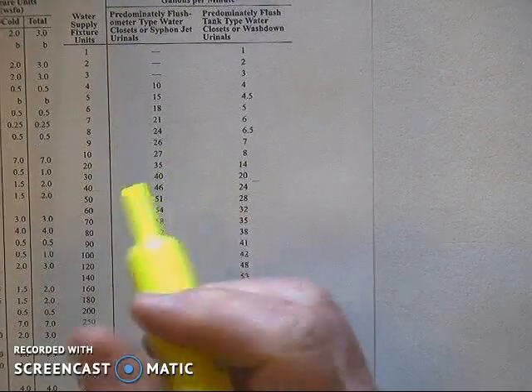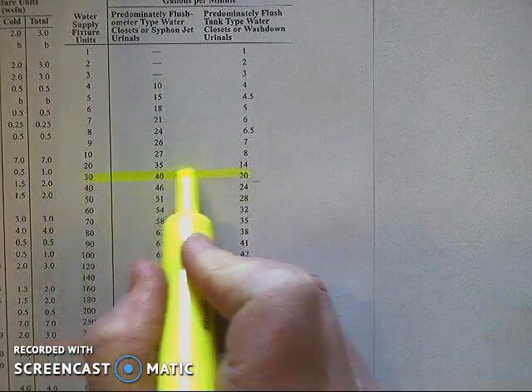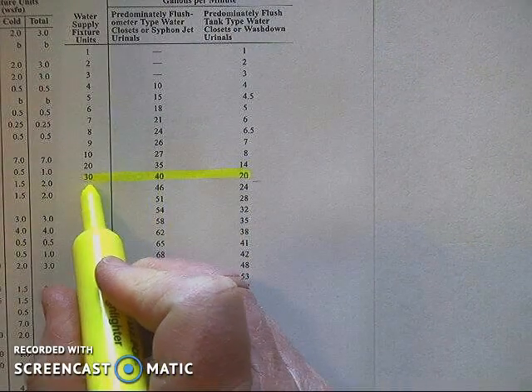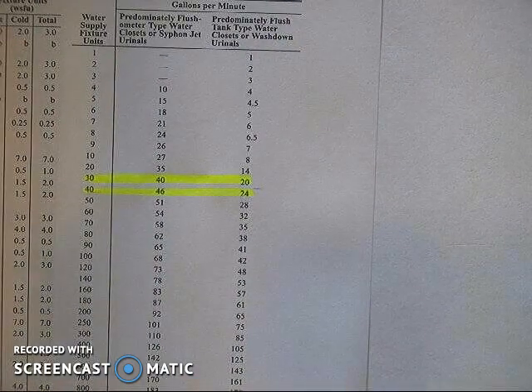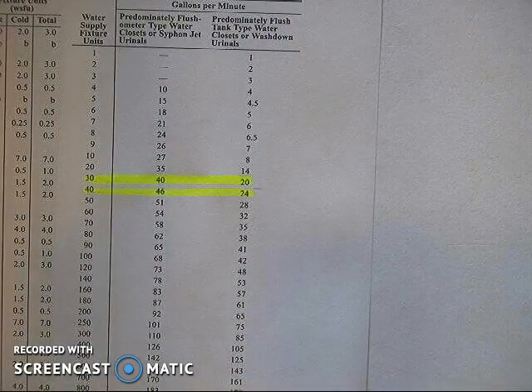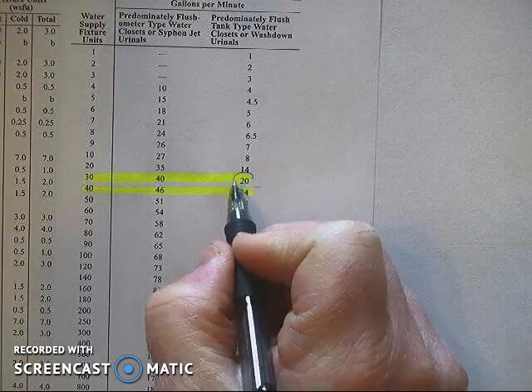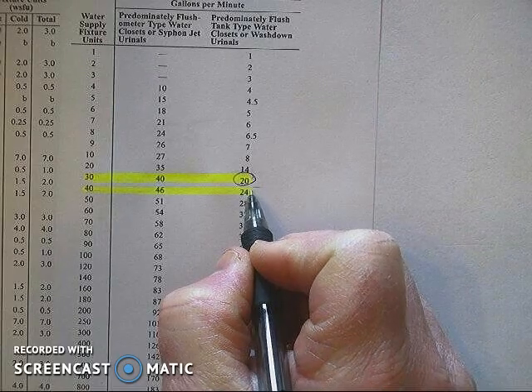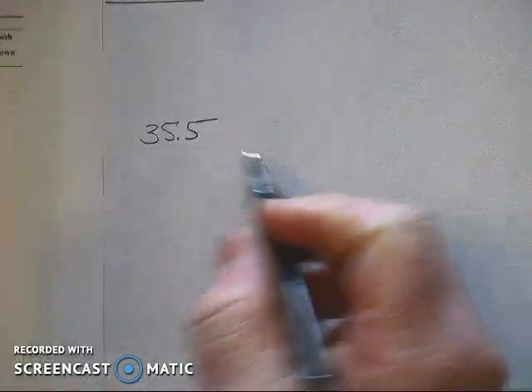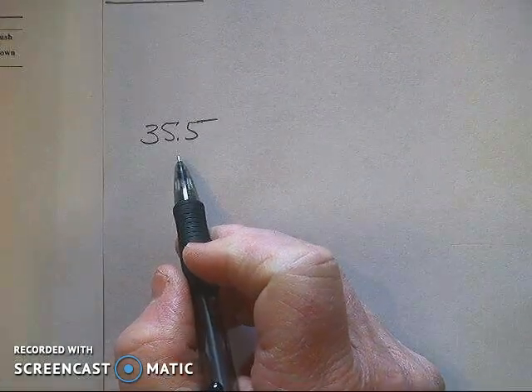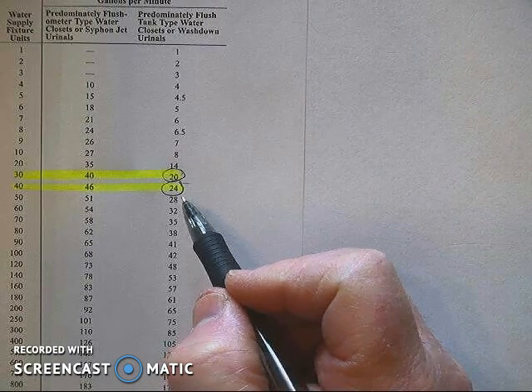What I'm going to do is quickly highlight that I do know the gallons per minute for 30 WSFU and I do know the gallons per minute for 40 WSFU. You'll notice on the right hand side 30 WSFU equals 20 GPM and 40 WSFU equals 24 GPM. So our 35.5 WSFU is going to fall somewhere in between that 20 and 24 GPMs.